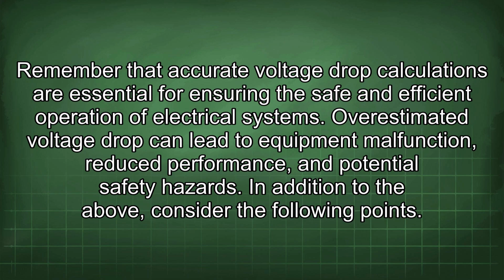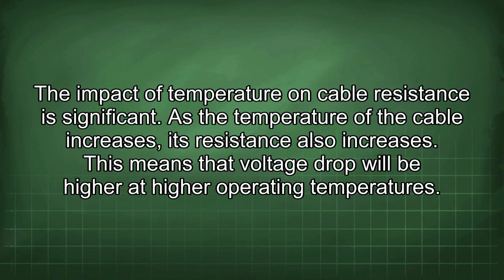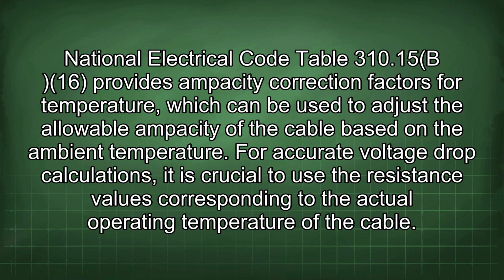In addition to the above, consider the following points. The impact of temperature on cable resistance is significant. As the temperature of the cable increases, its resistance also increases. This means that voltage drop will be higher at higher operating temperatures. National Electrical Code Table 310.15(B)(16) provides ampacity correction factors for temperature, which can be used to adjust the allowable ampacity of the cable based on the ambient temperature. For accurate voltage drop calculations, it is crucial to use the resistance values corresponding to the actual operating temperature of the cable.